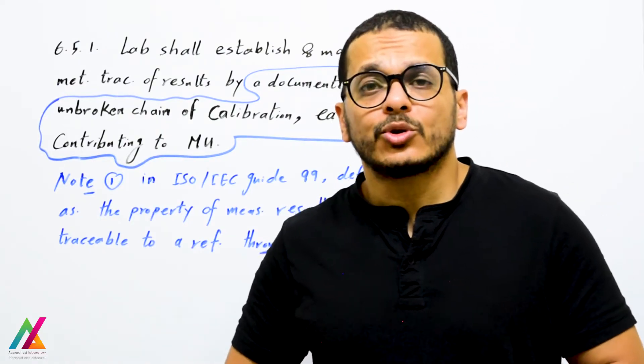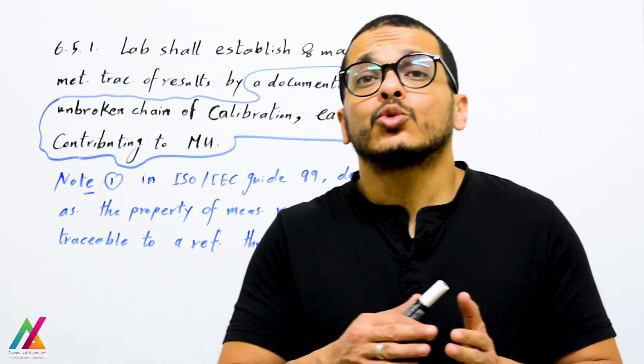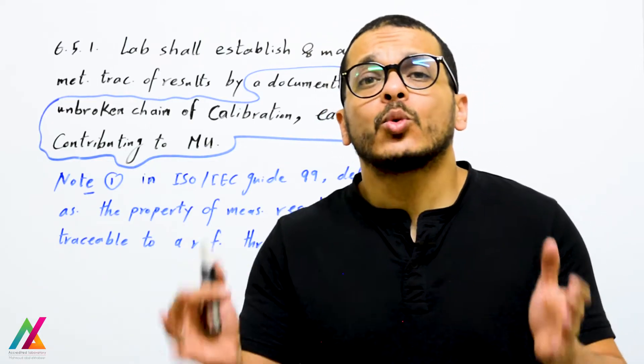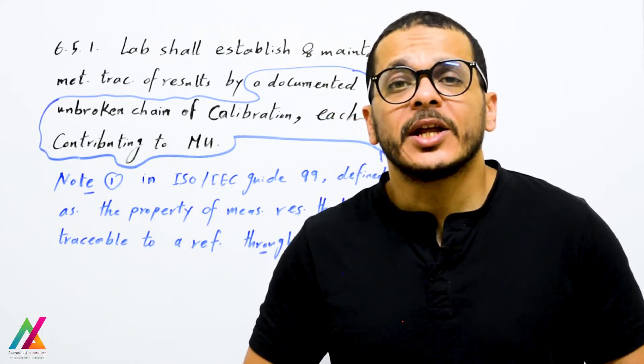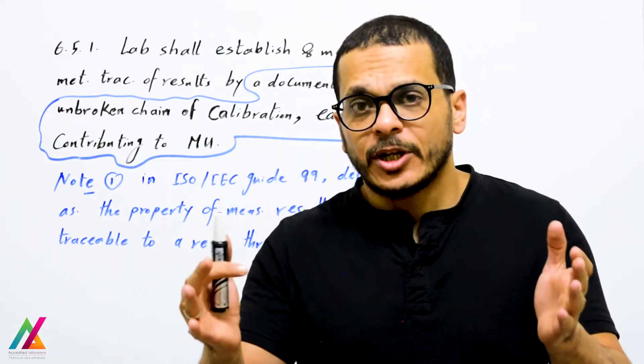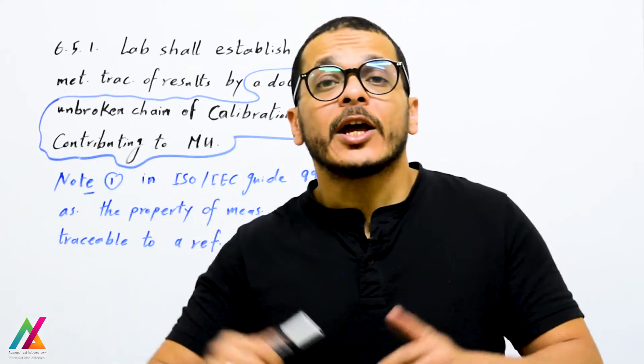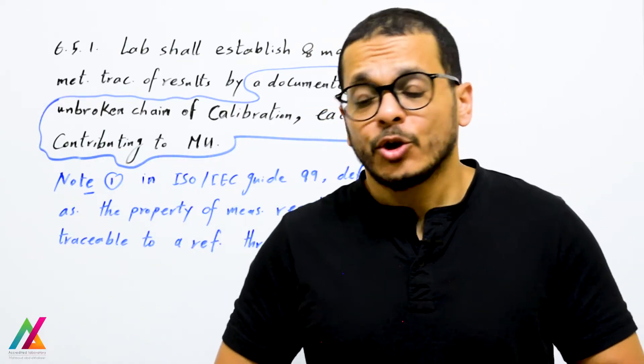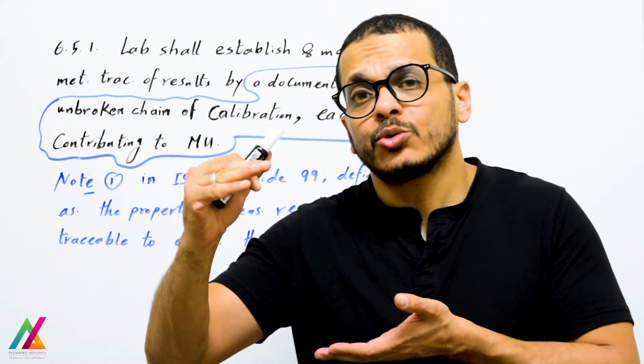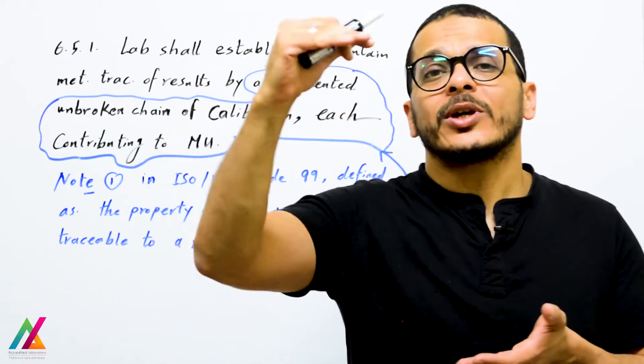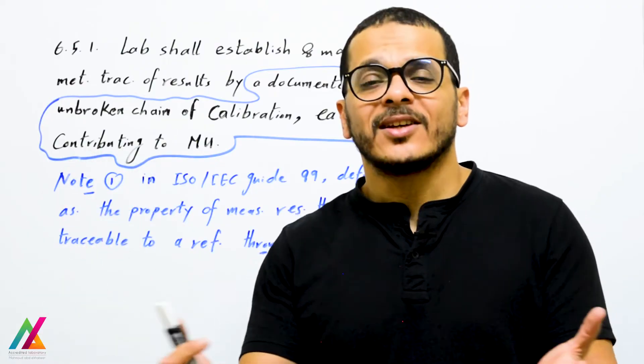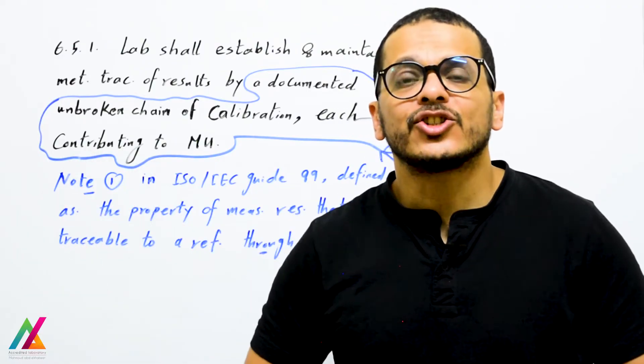To ensure metrological traceability of results to SI units, all equipment inside the lab shall be calibrated with a specific calibrator, which shall be calibrated by a competent calibration lab, which is traceable to the National Metrological Institute, which is traceable to SI units. This is the documented unbroken chain of calibration.